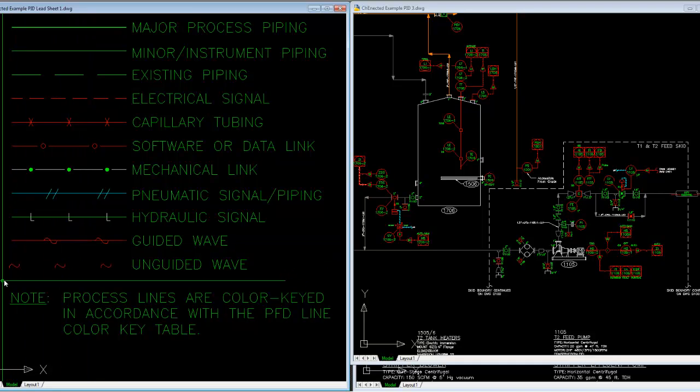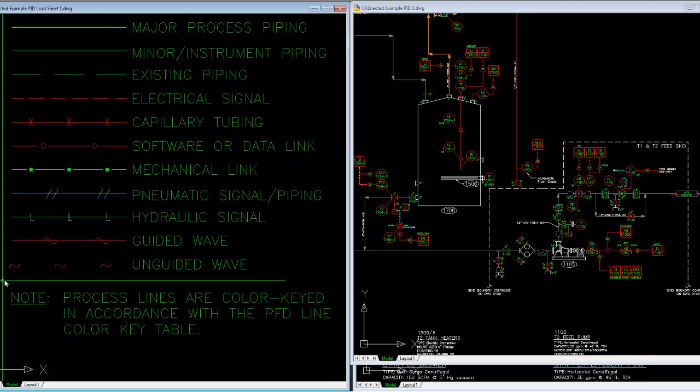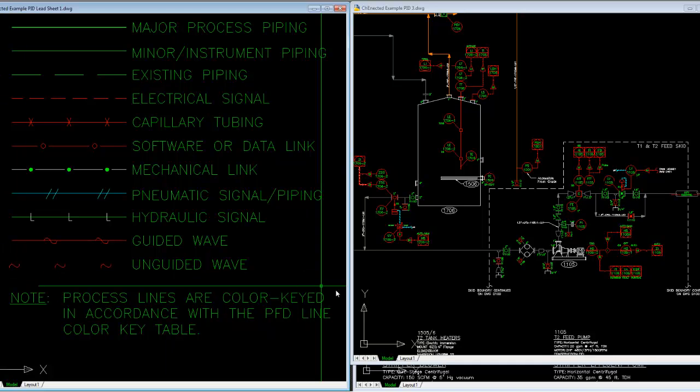On the other hand, you might have unguided radar with a transmission horn, transceiver that pulses and receives the signal back through the head space of the tank or ultrasonic level, which does the same. And it's unguided. It pulses and it's not guided or it reflects off some physical boundary and comes back. And you may show that in that manner.